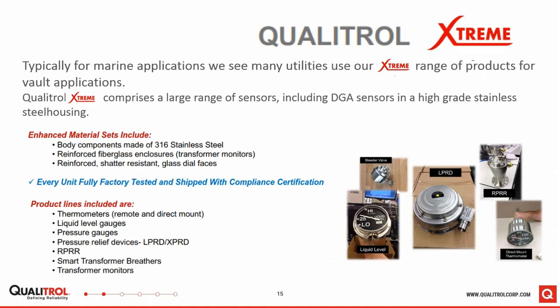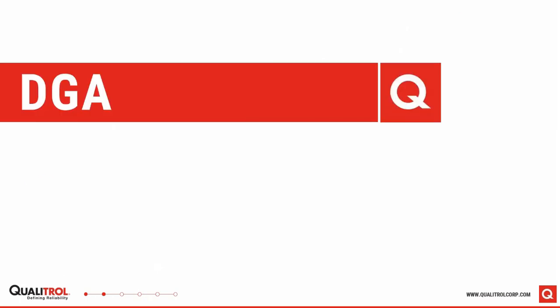And so we do have, for extremely corrosive environments, typically our standard sealed gauges work very well in vaults, but in areas that have extreme corrosion, possibly in saltwater areas, or if you're near some type of refinery or chemical plant, we do have a full line of stainless steel products, from pressure relief devices, pressure bleeders, sudden pressure relays, and a full line of stainless gauges. So that's called our Qualitrol XTREME product line. The next slide, please. So now Donal will talk about specifics on our DGA monitoring.